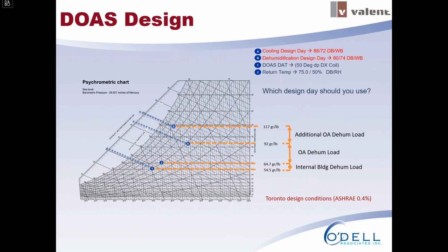So we've got state point A, which is our typical cooling design day in Toronto, 88/72. Those are in Fahrenheit, dry bulb, wet bulb. And that's a pretty typical condition used for packaged refrigeration, rooftop units. But what we see when we're just laying out DOAS units is we really want to be using the dehumidification design day conditions, which in Toronto is more typically about 80 degrees, 74 degrees, dry bulb, wet bulb. And with the DOAS unit, you can see there's state point 1 on the psych chart. That's our target. That's what we're trying to dehumidify down to.